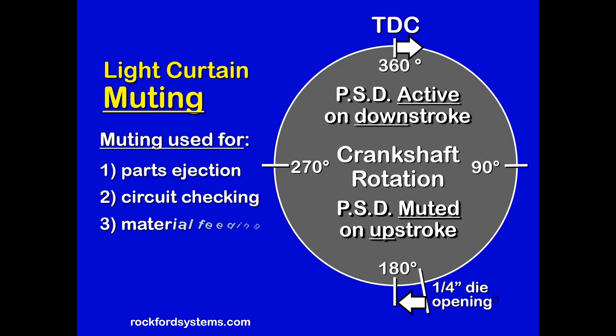Two things you can do with light curtains: muting and blanking. Muting means you automatically shut off the light curtain during the non-hazardous portion of the cycle, assuming there is a non-hazardous portion of the cycle. So it's got to be active for the hazardous portion. You can shut it off or mute it during the non-hazardous portion. Usually, speeding things up for productivity is the reason people mute a light curtain. Blanking is different, and blanking is oftentimes abused because people overdo it.